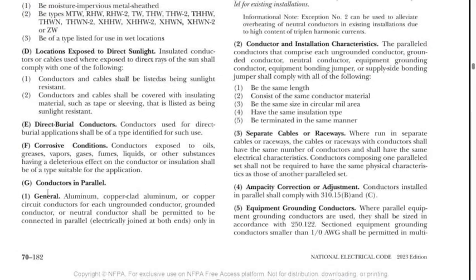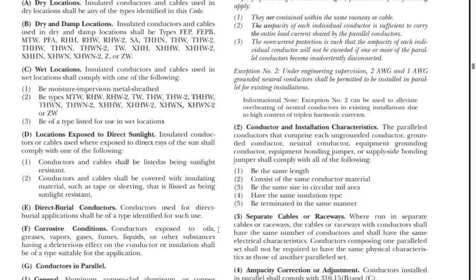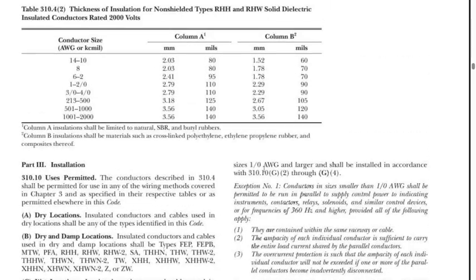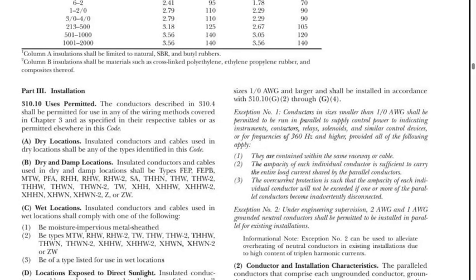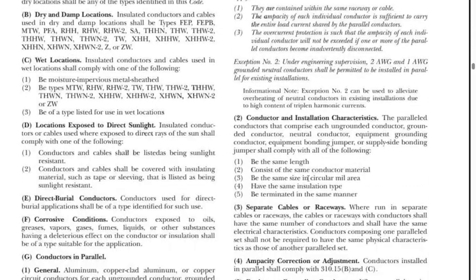All right, we looked at conductors in parallel. We sized some conductors for the parallel. We had a few rules that we had to consider. Parallel is 1/0 or larger. We can't go smaller than 1/0. So we had some things that we had to deal with. We also had some things that the conductors had to consider, which is same length, same size, conductor material, insulation, etc. But also no abnormal conditions.